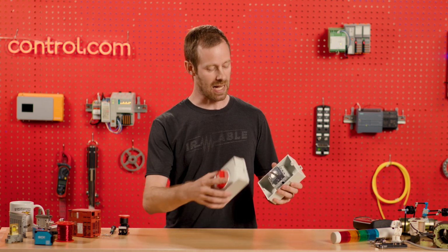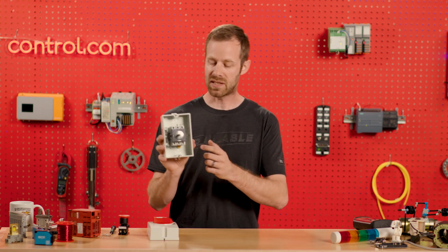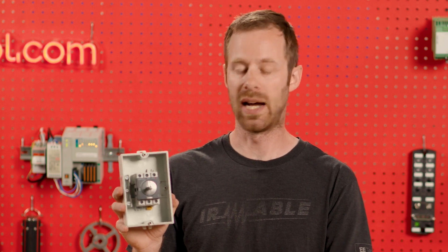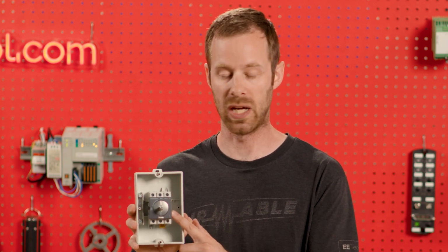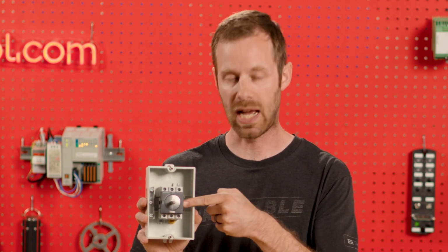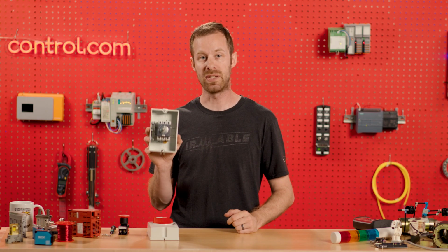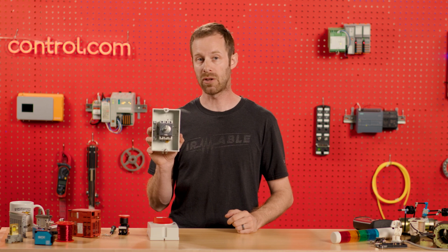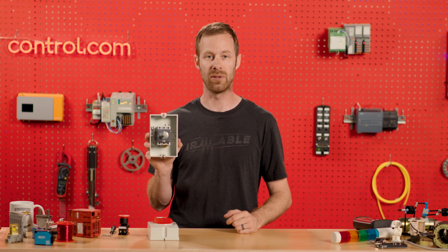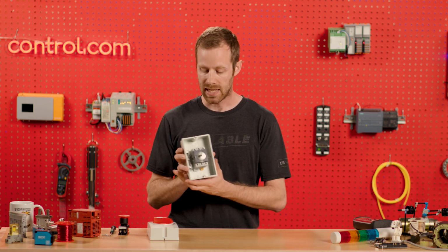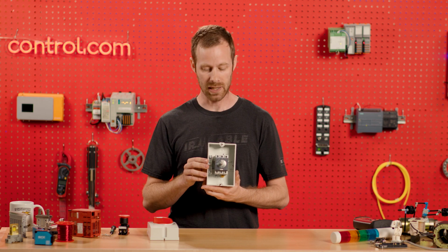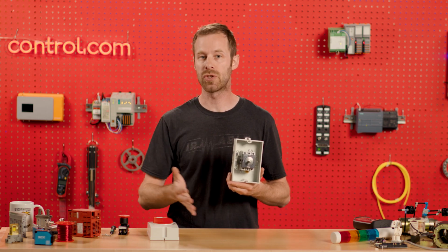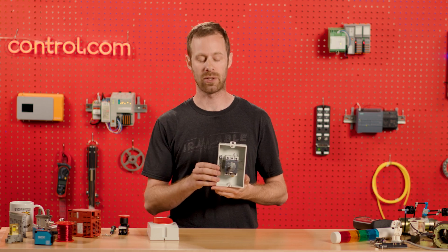Now, if we look inside, we see actually a smaller assembly inside. This is actually the disconnect switch. Often the disconnect switches can have handles that come in from the side, handles that come in from the front, and they look an awful lot like circuit breakers. But a disconnect by itself is neither fused nor has a circuit breaker inside. And what that means is that while you can turn it on and off, it will not provide automatic protection if the device downstream starts using too much electricity.